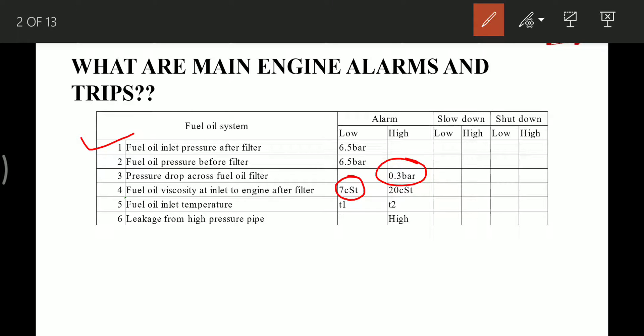Fuel oil viscosity at inlet to the engine after filter gives a low alarm at 7 cSt and high alarm at 20 cSt. Fuel oil inlet temperature depends upon the viscosity — both low and high temperature alarms are given. Last is leakage from high pressure pipes, which gives a high pressure alarm in case of leakage.